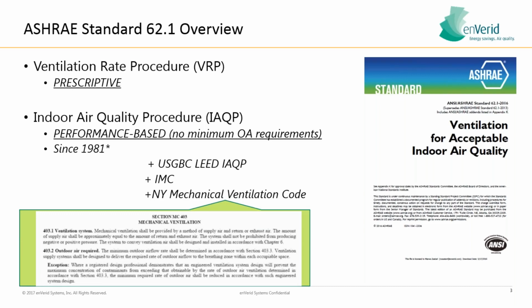A subsection within the ventilation rate procedure is demand control ventilation, and basically what this says is if occupancy varies within the space, you can place CO2 sensors within those areas. And when the space is not as densely occupied, you don't have to bring in as much outside air to ventilate the space because you're not flushing out the people component of those contaminants.